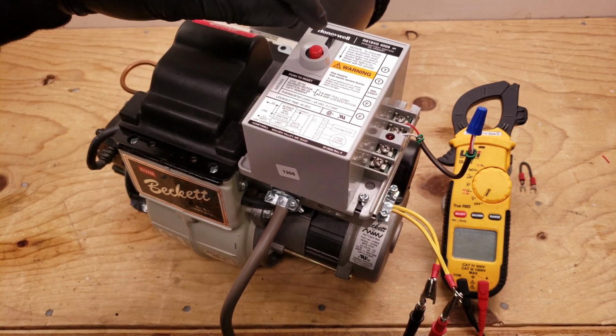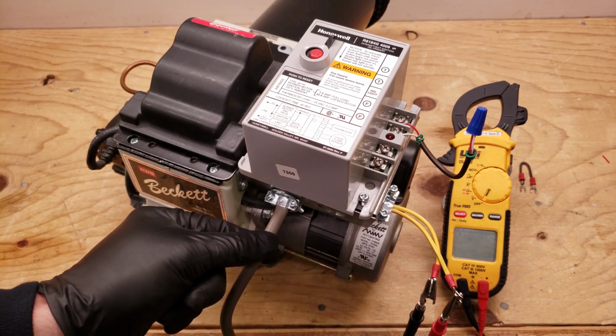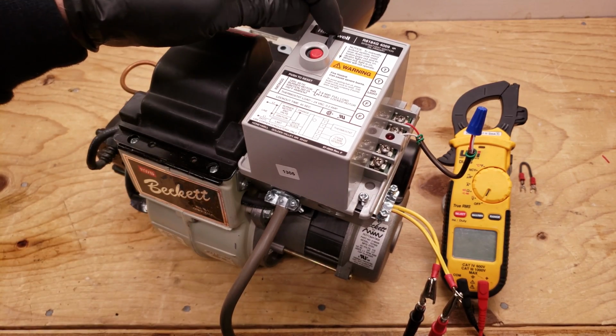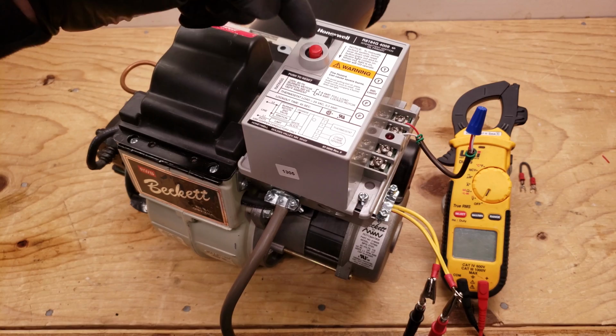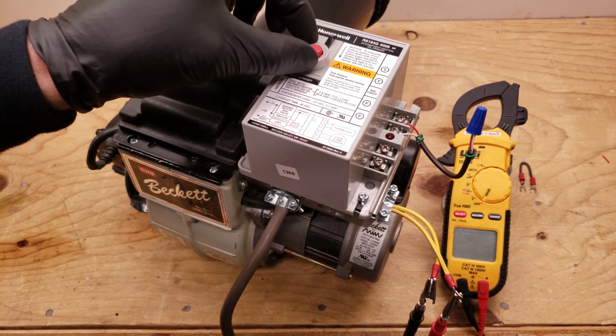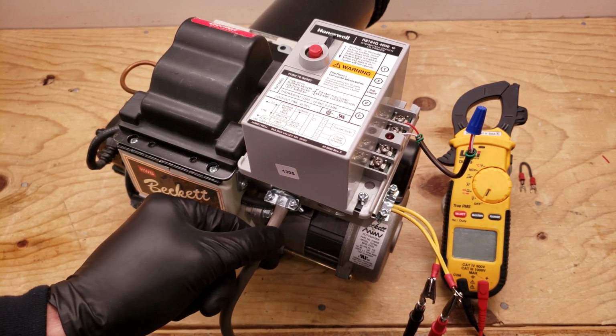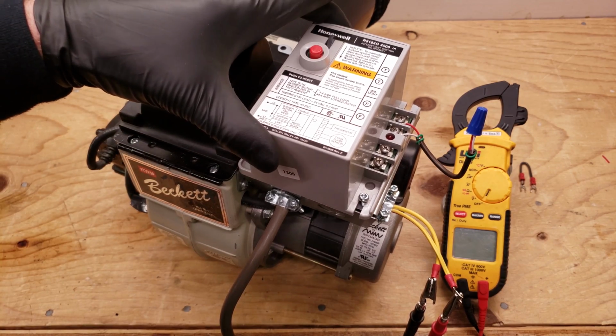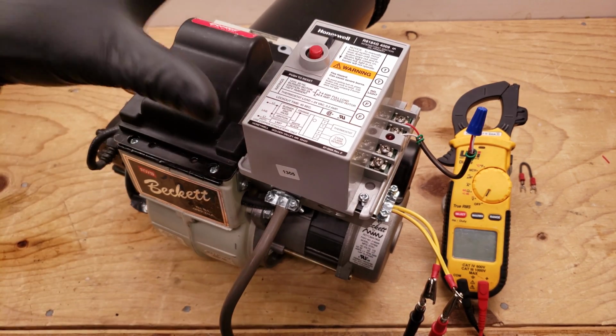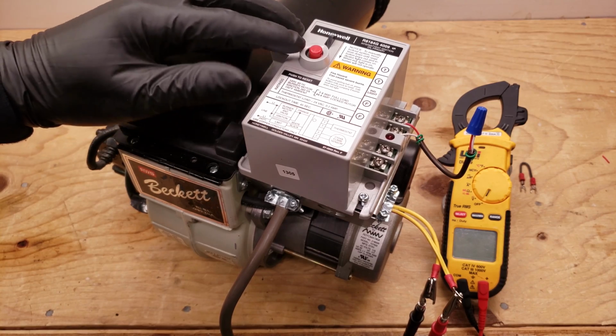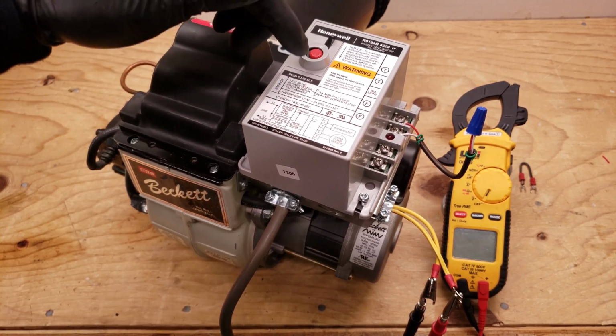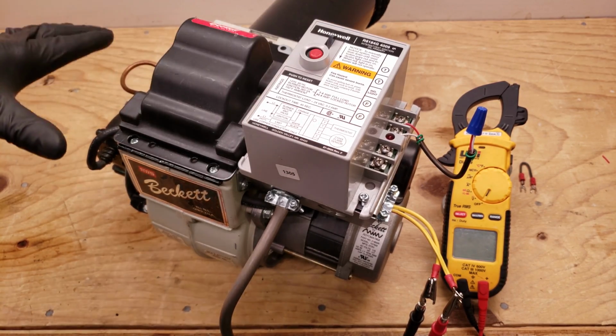You can press this reset button down regardless of whether you have incoming power or not. And also this lever right here will pop it back up into the reset position. So right now, if it does not have any power coming in, it's not going to allow the primary control to operate. During normal operation, if this keeps popping up on you, you want to make sure to not just keep pressing it down, because it's signaling that there's a problem here.